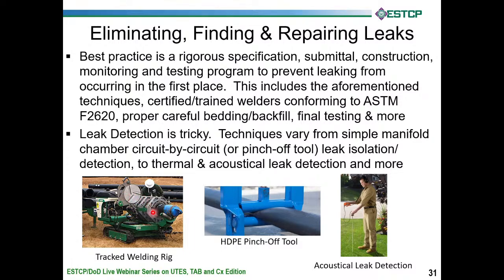But anyway, there's a series of heated plates here that melt the ends, and also to apply the proper pressure at that joint, these machines can load the piping axially so that it smashes the two melted ends together. And it's important that you get people who know what they're doing in the welding. But if you do, these are welded systems buried underground. They're not subject to corrosion, UV rot, or any of that. They can last you for decades, if not indefinitely.